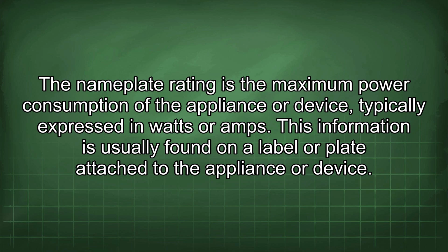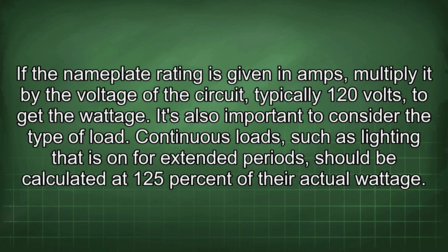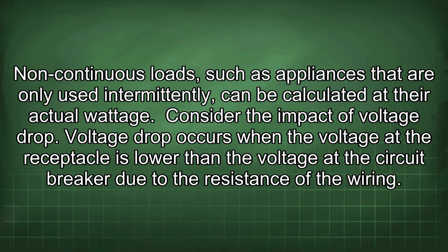This information is usually found on a label or plate attached to the appliance or device. If the nameplate rating is given in amps, multiply it by the voltage of the circuit, typically 120 volts, to get the wattage. It's also important to consider the type of load. Continuous loads, such as lighting that is on for extended periods, should be calculated at 125% of their actual wattage. Non-continuous loads, such as appliances that are only used intermittently, can be calculated at their actual wattage.